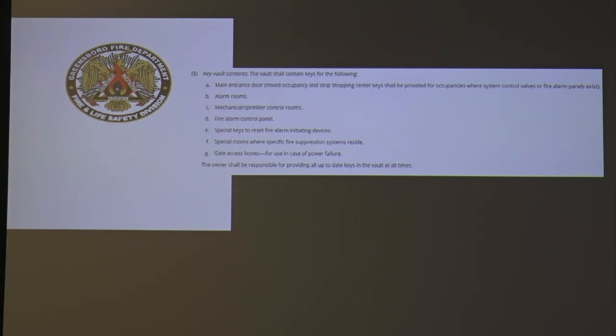We have several places. Our district inspectors are slowly but surely working through it. I know that in Darren's territory, off of Bridford Parkway, there are a couple of apartments that have already been upfitted. What's the one right there at Bridford and Hilltop? The Lakes. When you put the keys in, those gates open. That used to be siren activated. I was doing a CO in the clubhouse and I said, this is no longer acceptable. For me to CO your building, I'm holding you up on your gates. They had the keys in there in about three days.